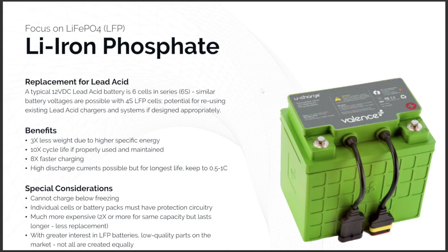Because of the chemistries, and for safety, cells or battery packs must have protection circuitry, because you don't want a thermal runaway. It's more expensive, but on the flip side, it lasts longer, so you may replace the battery less. And because this is where everyone is very focused lately, your mileage may vary with suppliers. You really have to do some research, because everyone wants to make lithium iron phosphate batteries. So you've got to see what's out there on the market - there might be some lower cost options, but then, is the quality there?